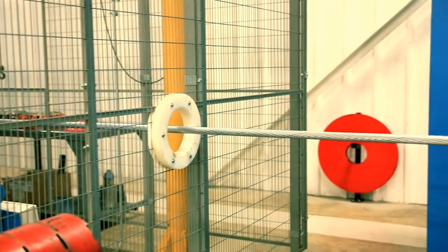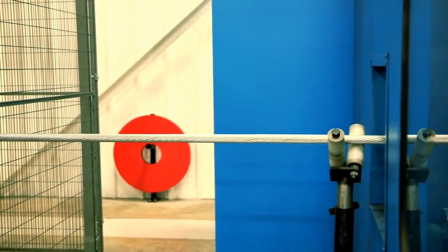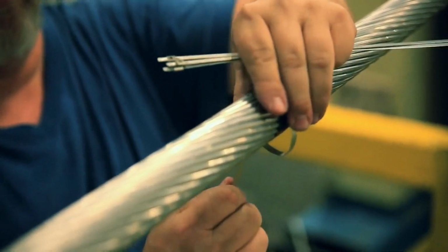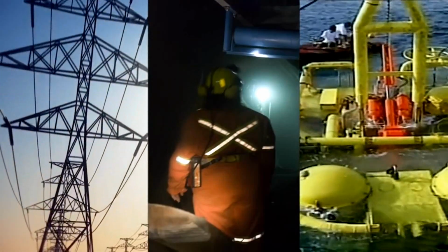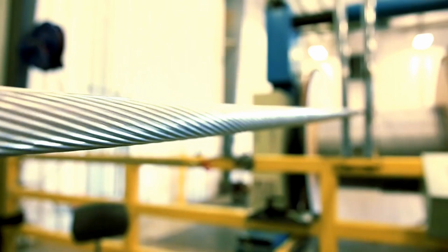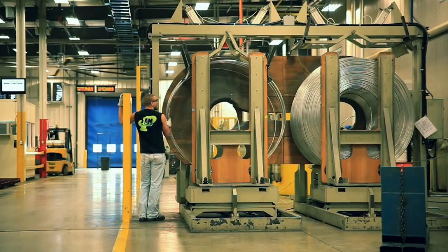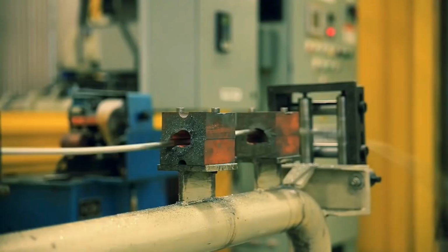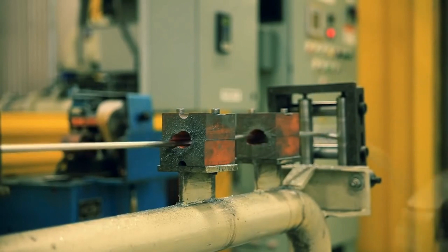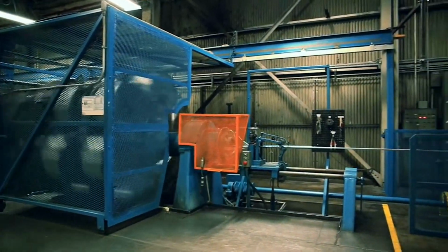General Cable also manufactures a complete line of energy cables, including low, medium, high, and extra high voltage power distribution and power transmission products for overhead, underground, or subsea applications. While much larger in scale, most of these cables proceed through a similar manufacturing process, with the exception of bare overhead aluminum conductors. These high and extra high voltage transmission cables are produced by drawing aluminum rod to the proper size or gauge and then stranding the conductor to the exacting specification of the overhead conductor's design.